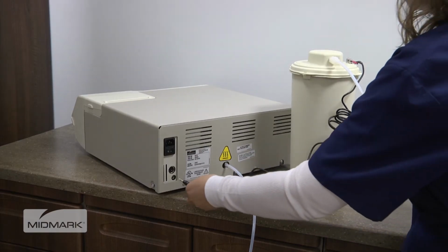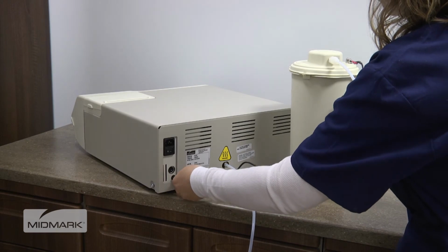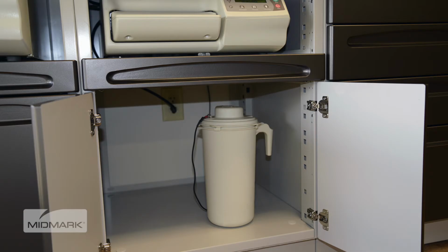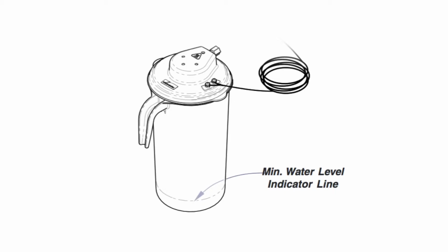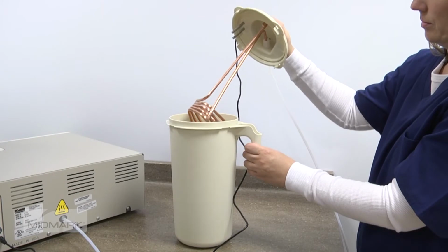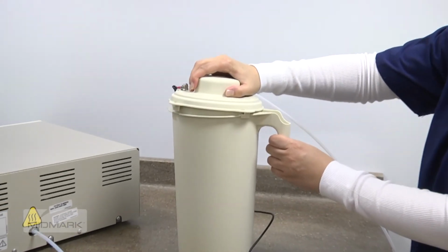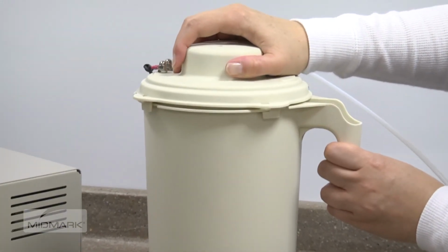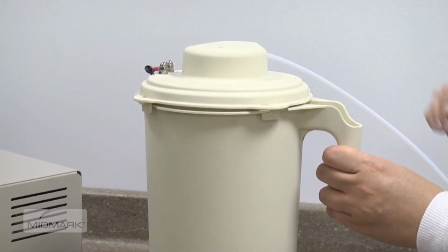Next, connect the sensor plug to the port on the back of the autoclave. Place the tank on a level surface, no higher than the sterilizer support surface. Fill the tank with tap water to the minimum water level indicator line. Insert the lid assembly into the pitcher. Align the tabs for correct positioning, and rotate clockwise to secure.